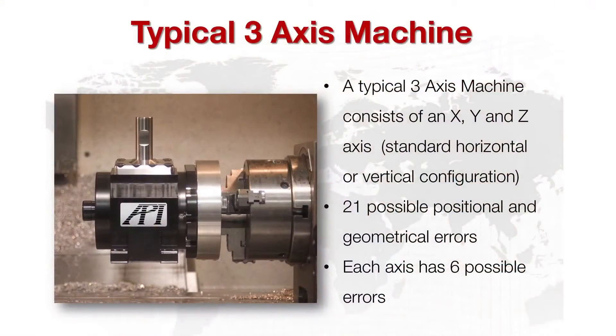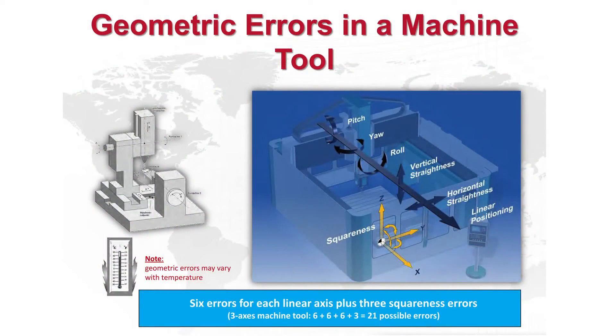A horizontal or vertical typical three-axis machine tool would have six errors for each one of the axes — X, Y, and Z — for a total of 18, plus three possible squareness errors, for a total of 21 errors.